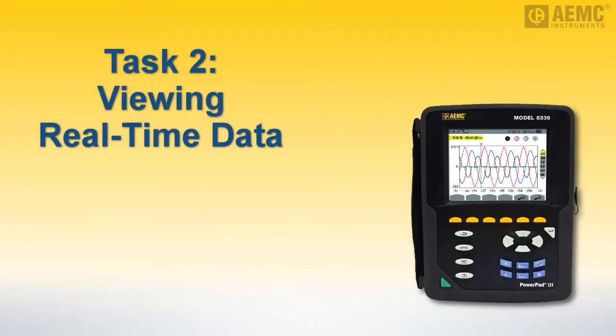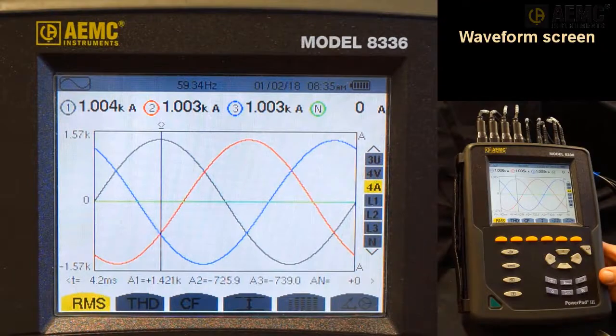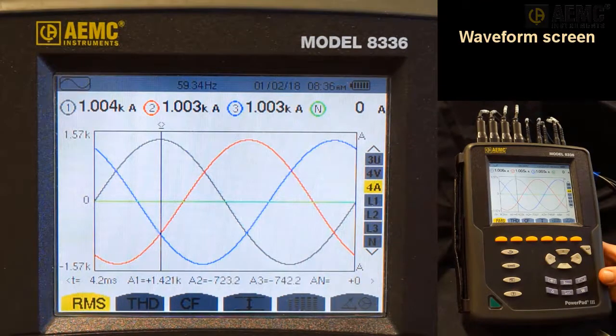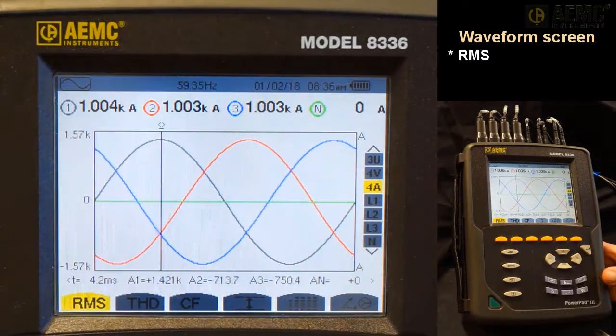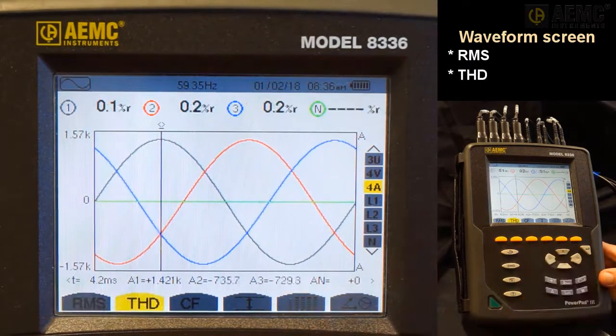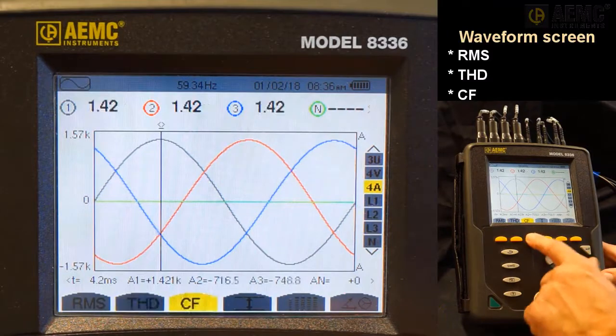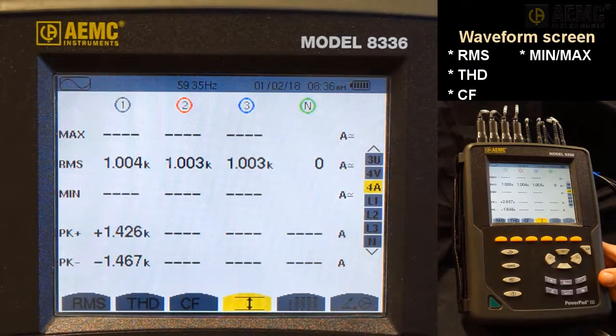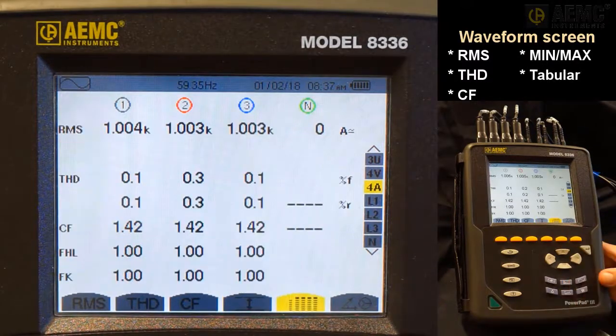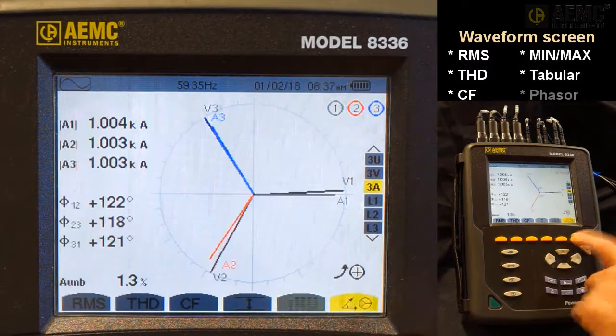With the Model 8336 configured and connected to a hookup, or in our case, a hookup simulation, we can now view measurement data in real-time. For instance, the default display screen that appears when you first power on the Model 8336 is the waveform screen. This screen includes its own set of function button icons for displaying true RMS values, total harmonic distortion calculations, crest factor values, minimum, maximum, RMS, and peak values, a variety of measurements in tabular format, and a real-time phasor diagram.